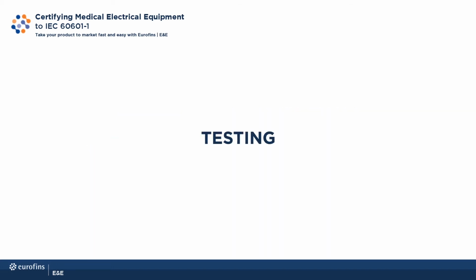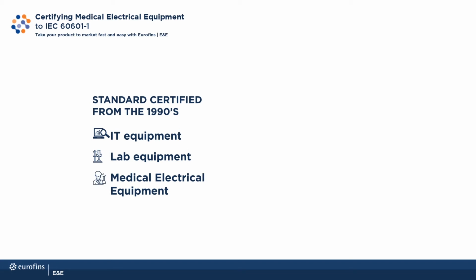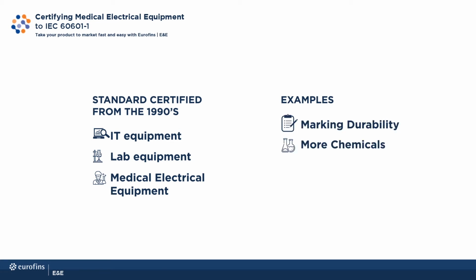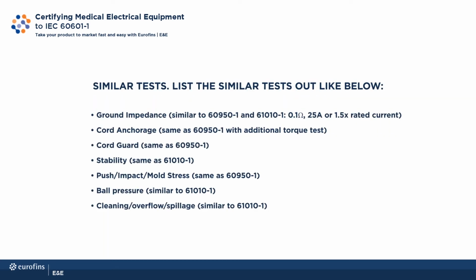So now let's talk about testing. If you have ever certified IT equipment, lab equipment, or certified medical electrical equipment to the standard from the 1990s, a lot of the tests in today's medical standard are very similar. Sometimes, though, they are more stringent. Examples include marking durability, which requires more chemicals, accessibility, which requires a test hook, and cap discharge, which requires a faster decay.